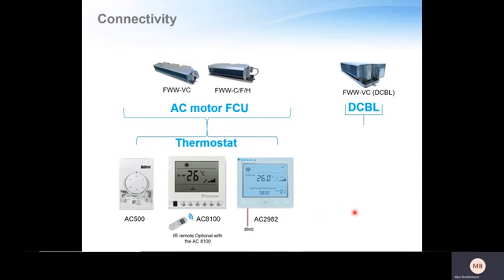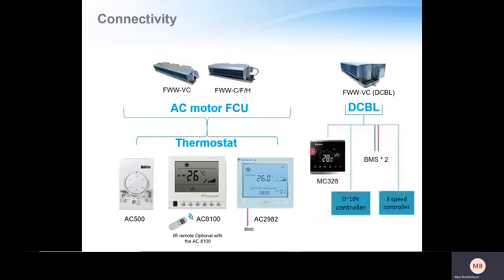If the inverter model fan coil is selected, we offer this remote control. It comes with BMS adaptability as well as a 3-speed controller, or we offer a 0 to 10 volt signal, which offers optional linear fan speed control. So this will be gradual. It will just be linear up and down, but you'd need a third-party controller to drive the fan for the commutation.